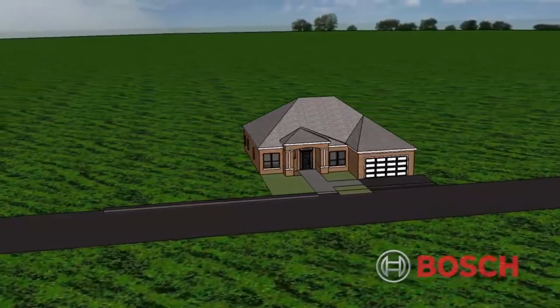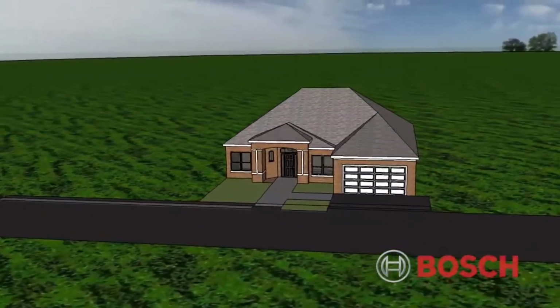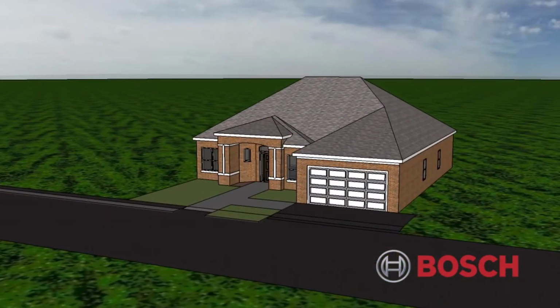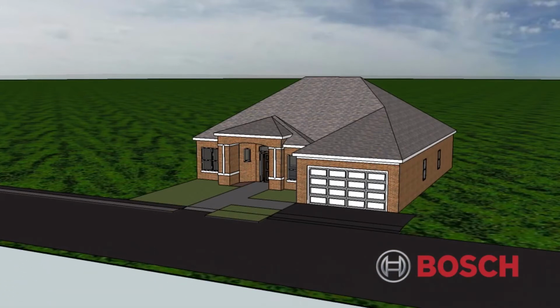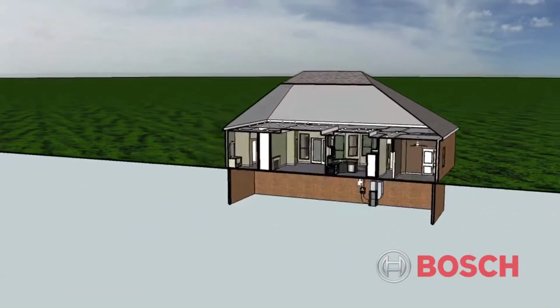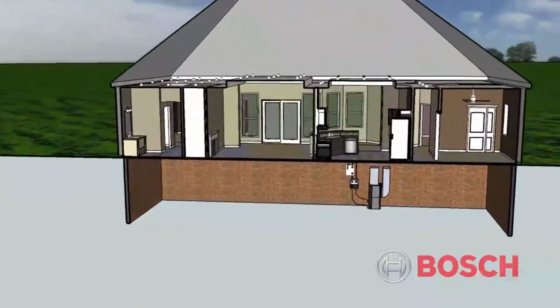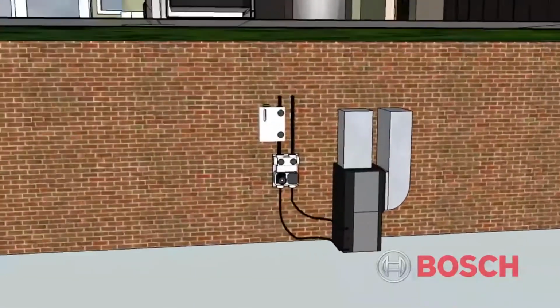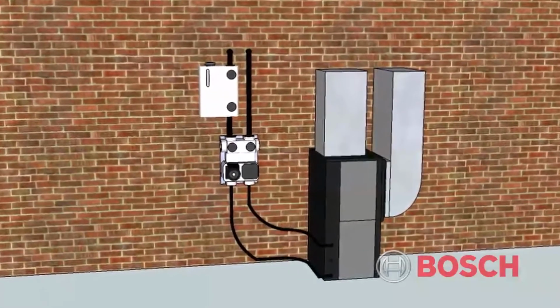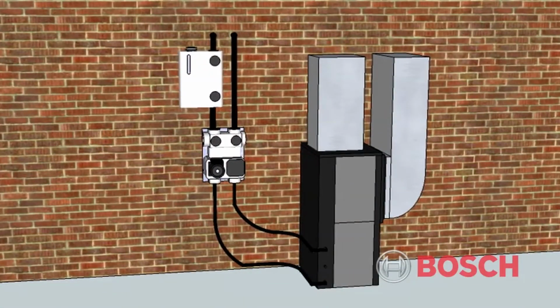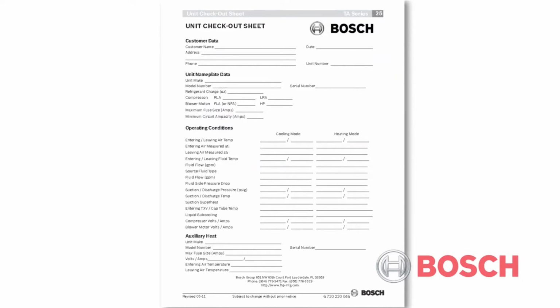For this system, we'll be using a water-only solution because this installation is in a southern climate and the minimum entering loop temperatures never drop below 42 degrees Fahrenheit. In areas where the minimum loop temperatures drop below 42 degrees Fahrenheit, or when the piping will be routed through areas subject to freezing, an antifreeze solution is required. When using an antifreeze solution, we'd have to calculate the freeze protection percentage based on the total volume of fluid. For more details on this process, please reference the installation manual.